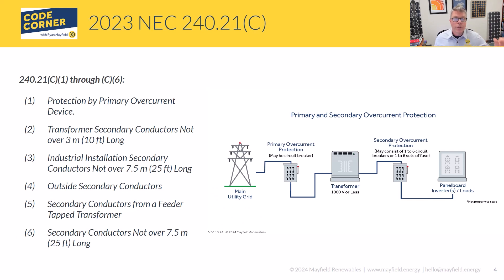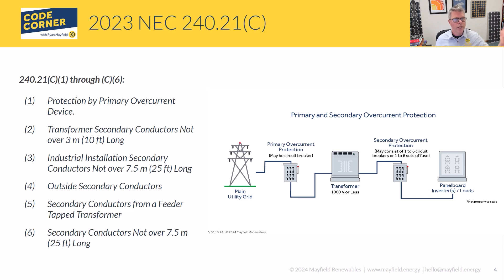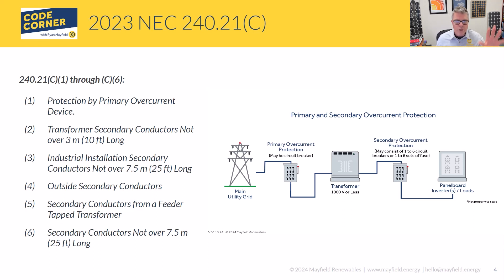240.21C1 through C6 gives six different scenarios with rules that apply differently. C1: protected by a primary overcurrent device — in PV systems this almost universally does not apply. C2: conductors not more than 3 meters or 10 feet long. C3: industrial installations. C4: outside conductors. C5: secondary conductors from a feeder, pointing back to 240.21B. C6: secondary conductors not over 25 feet or 7.5 meters. You'll need to go through each based on the length of your feeder conductors to understand which applies.